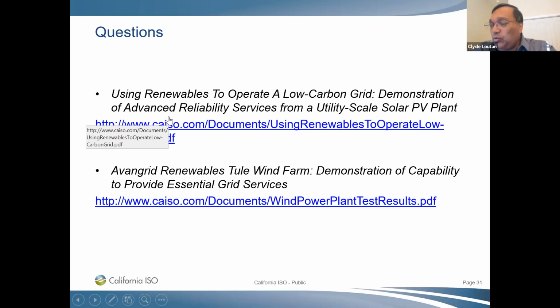Because as I mentioned, if you have a contingency, we only have 15 minutes to recover ACE, the area control error, to where it was prior to that event. If you take longer than 15 minutes, like 15 minutes and 10 seconds, let's say, that's a violation. And you could get fined pretty heavily by the North American Electric Reliability Corporation or even FERC. We have not been fined yet, so it's something you take very, very seriously. You want to make sure you have enough contingency reserve, because a violation could come with up to $1 million in fines per event.